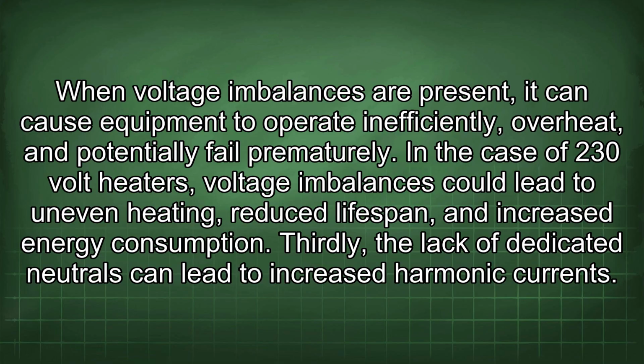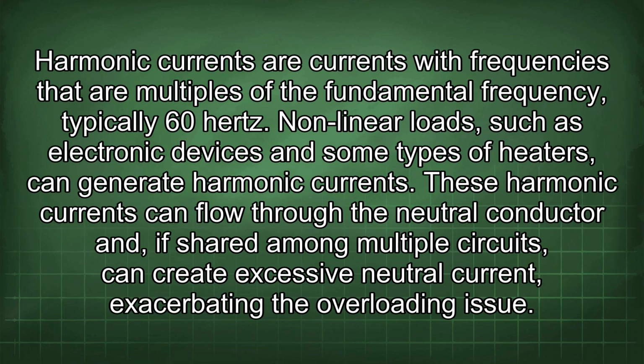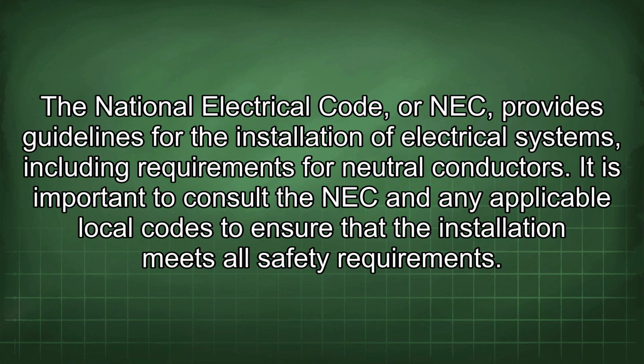Thirdly, the lack of dedicated neutrals can lead to increased harmonic currents. Harmonic currents are currents with frequencies that are multiples of the fundamental frequency, typically 60 Hz. Nonlinear loads, such as electronic devices and some types of heaters, can generate harmonic currents. These harmonic currents can flow through the neutral conductor and, if shared among multiple circuits, can create excessive neutral current, exacerbating the overloading issue.